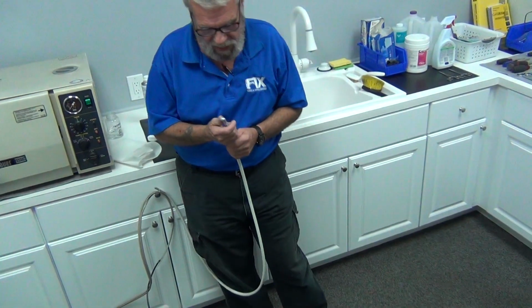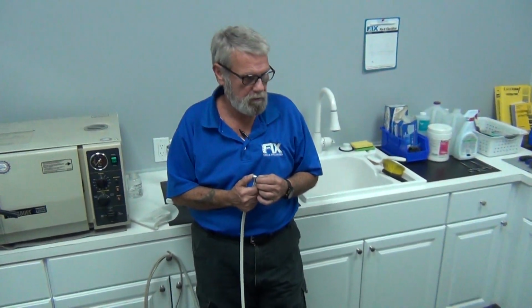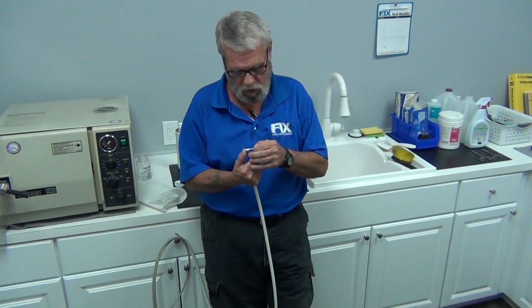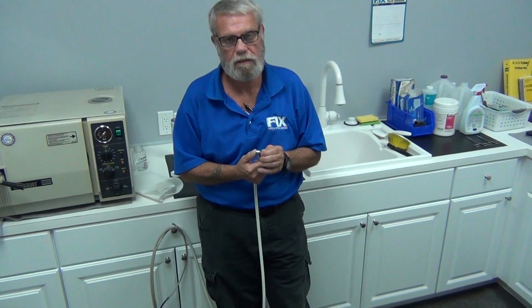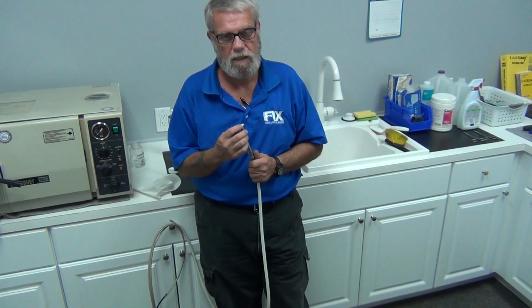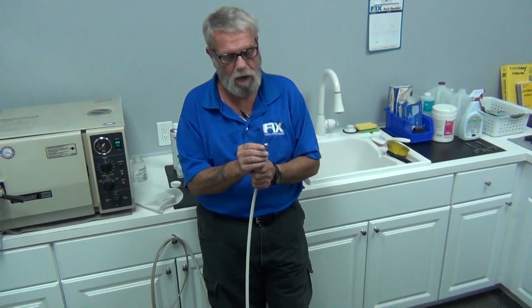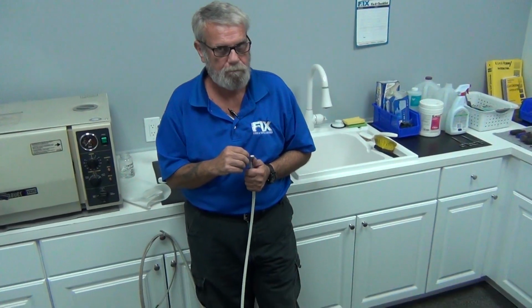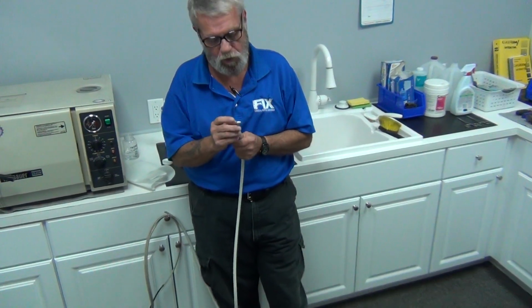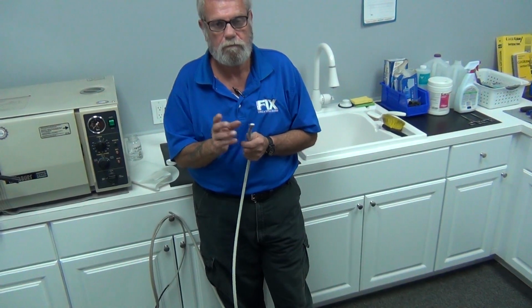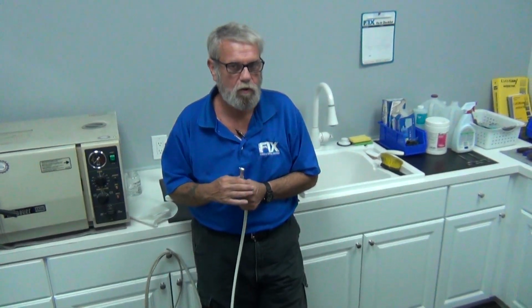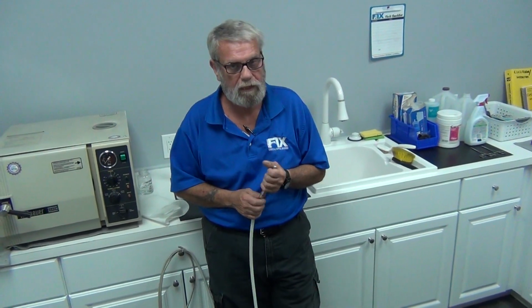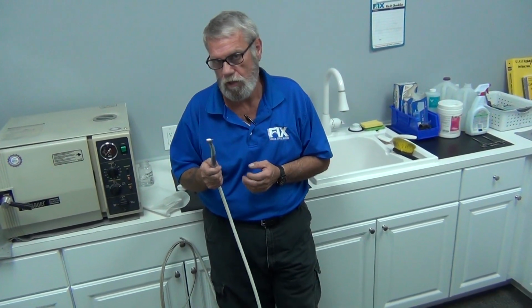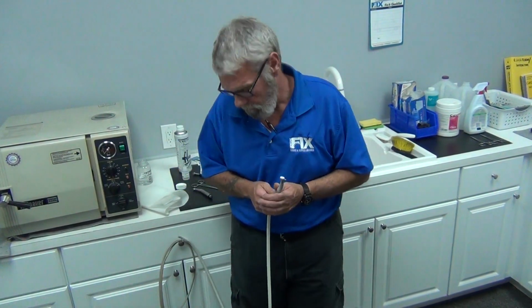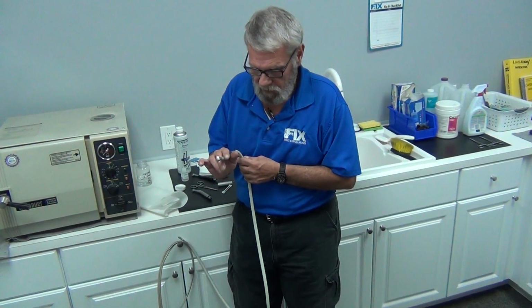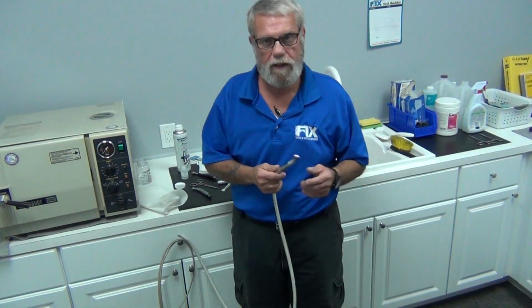Always stress to the office staff that it is so very important to seat the burr in all the way until it bottoms out. It's an unsafe condition if they don't. You want that burr bottomed all the way in that handpiece. Otherwise you'll get a burr not being concentric, or you will get burr whip. It will damage your turbine and your hard work on that turbine impeller that you built out in the truck to put in here. If that burr's not all the way in, it will throw it off balance and you'll have problems. We're going to do a light, nice little purge again. We're ready for sterilization.